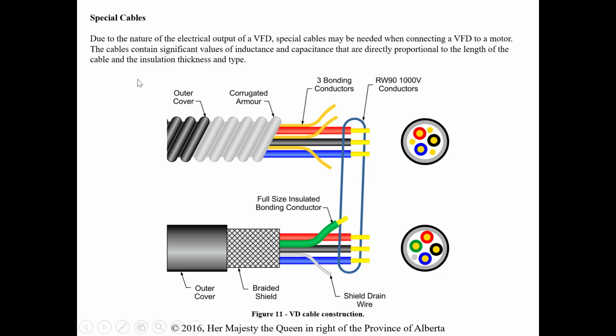Special cabling. Due to the nature of the electrical output of a VFD, special cables may be needed. The cables contain significant values of inductance and capacitance that are directly proportional to the length of the cable and the insulation thickness and type. So they talk about the cabling and also the bonding that's in there. In the top graph, you'll see they have 3 separate bonding conductors, and that helps to reduce the frequencies. Basically, they say that the radio frequency can be reduced by having multiple bonds, or they will have a bonding wire that is the same size as the conductors for the rest of the circuit. So we'll see a large bonding conductor, not what we would commonly see in a regular cable.